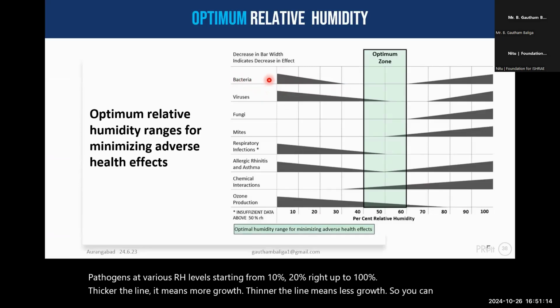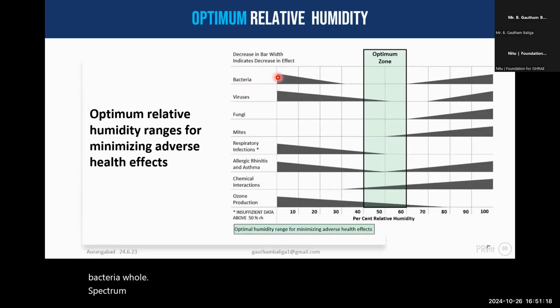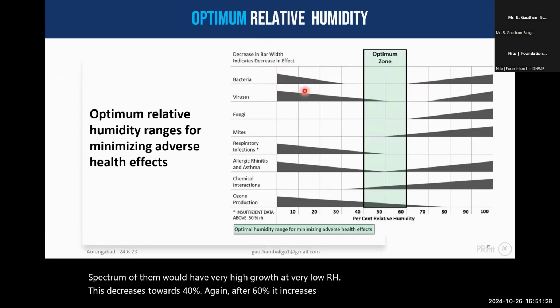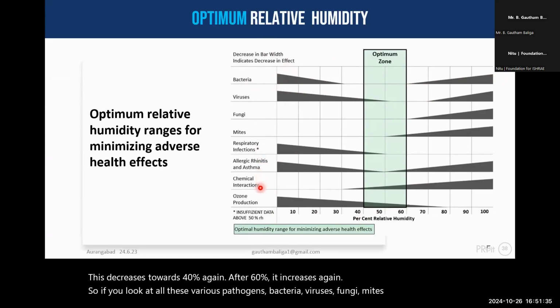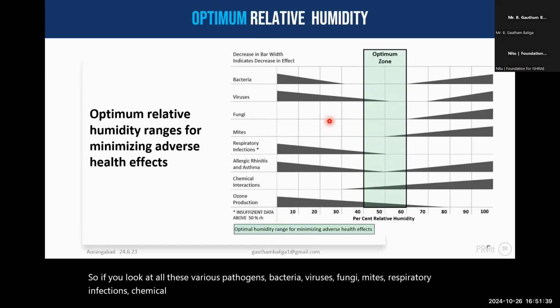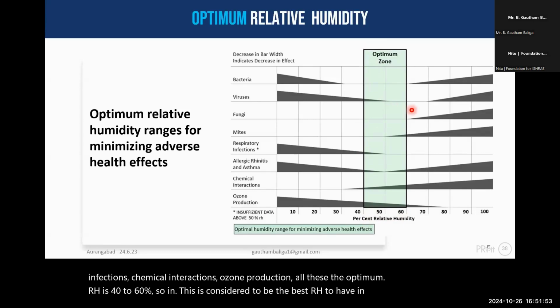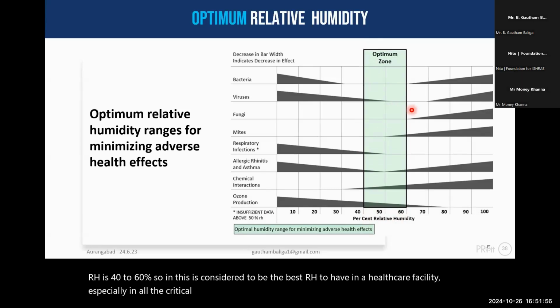So you can see bacteria, the whole spectrum of them would have very high growth at very low RH. This decreases towards 40%. Again, after 60%, it increases again. So if you look at all these various pathogens, bacteria, viruses, fungi, mites, respiratory infections, chemical interactions, ozone production, all these, the optimum RH is 40 to 60%. So this is considered to be the best RH to have in a healthcare facility, especially in all the critical areas, such as your ICUs, isolation rooms, then operation theaters. You should definitely have control between 40 to 60% RH.